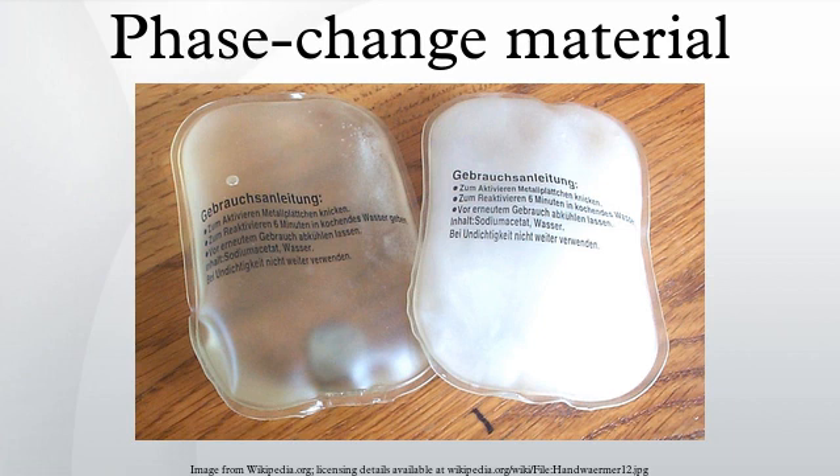This system can be considered a phase change slurry. Molecular encapsulation is another technology developed by DuPont de Nemours that allows a very high concentration of PCM within a polymer compound. It allows storage capacity up to 515 kilojoules per meter squared for a 5 mm board. Molecular encapsulation allows drilling and cutting through the material without any PCM leakage. As phase change materials perform best in small containers, they are usually divided in cells. The cells are shallow to reduce static head, based on the principle of shallow container geometry. The packaging material should conduct heat well and be durable enough to withstand frequent changes in the storage material's volume. It should also restrict the passage of water through the walls. Packaging must also resist leakage and corrosion. Common packaging materials showing chemical compatibility with room temperature PCMs include stainless steel, polypropylene and polyolefin.